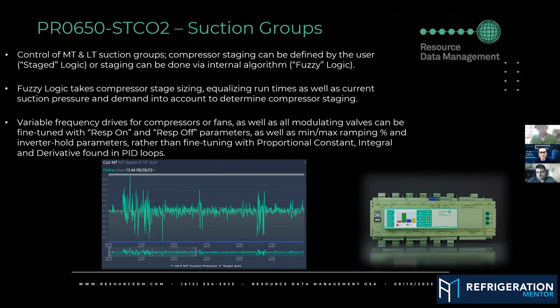What will happen is it'll send that signal to the valve, and the valve's trying to speed up, slow down, and then finally it just loses its steps. Then you'll look at the graph and the chart, and it says it's at 570. Well, it isn't at 570. It's actually at 1260, or vice versa. You just got to be real careful with these settings, and you got to watch this stuff.